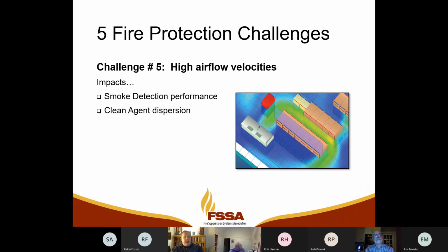Well, we've done some math on some of the data centers that we've been involved in, and in some of those situations we can exceed that in some portions of the system, meaning that the spot smoke detectors, if we're using photoelectrics, may not be rated for the air velocity that's moving by them, which then makes their effectiveness questionable.